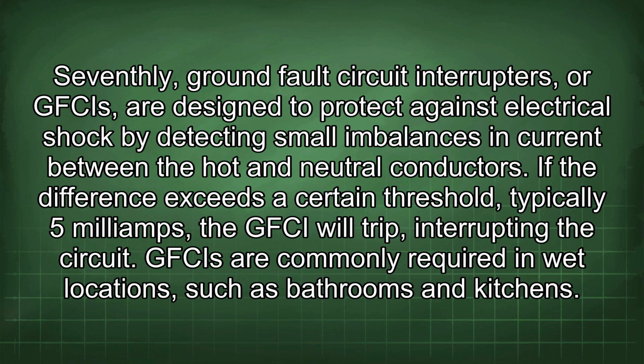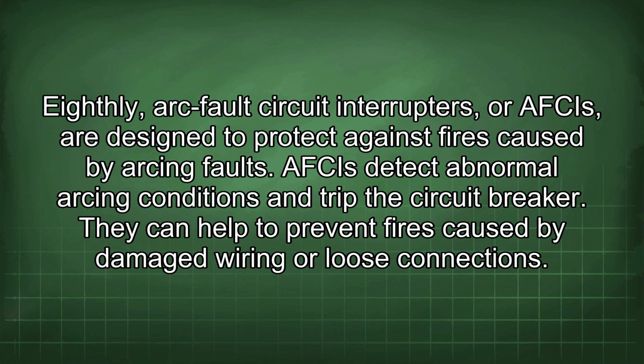Seventhly, ground fault circuit interrupters, or GFCIs, are designed to protect against electrical shock by detecting small imbalances in current between the hot and neutral conductors. If the difference exceeds a certain threshold, typically 5 mA, the GFCI will trip, interrupting the circuit. GFCIs are commonly required in wet locations such as bathrooms and kitchens. Eighthly, arc fault circuit interrupters, or AFCIs, are designed to protect against fires caused by arcing faults. AFCIs detect abnormal arcing conditions and trip the circuit breaker. They can help to prevent fires caused by damaged wiring or loose connections.